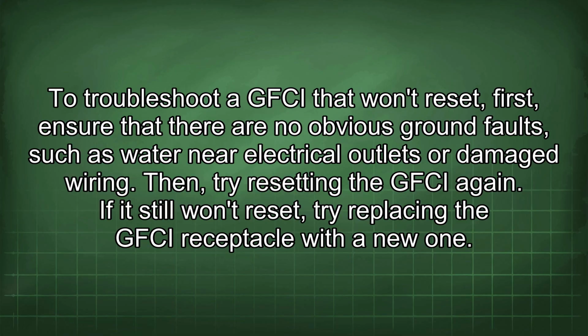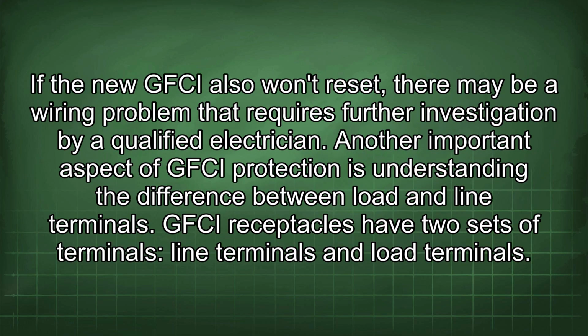Then try resetting the GFCI again. If it still won't reset, try replacing the GFCI receptacle with a new one. If the new GFCI also won't reset, there may be a wiring problem that requires further investigation by a qualified electrician.